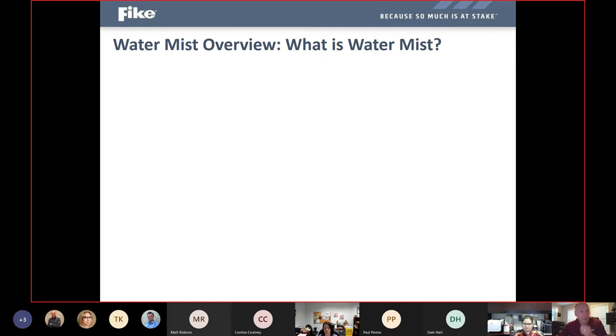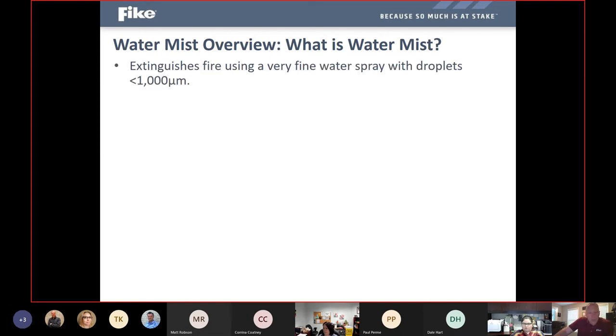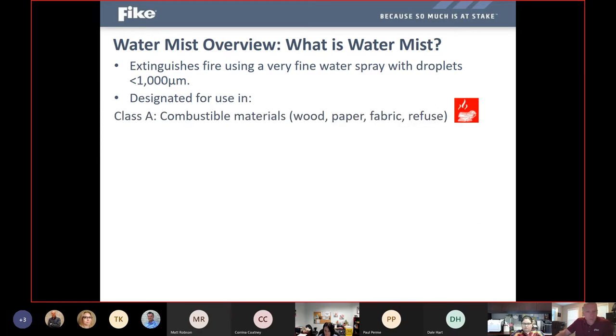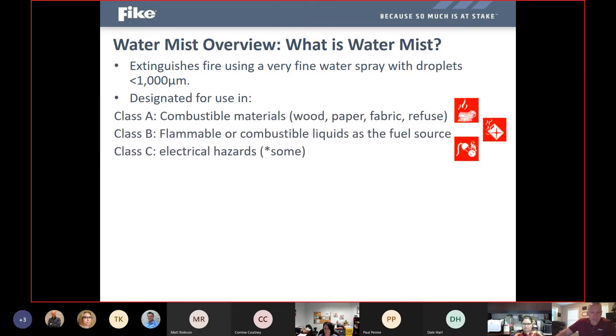One of the other newer and increasingly popular products is water mist. Water mist is what we define as a system that uses very fine water spray droplets, less than 1,000 microns in droplet size. That is what designates something as water mist. Water mist can be used in class A, B, and C hazards.